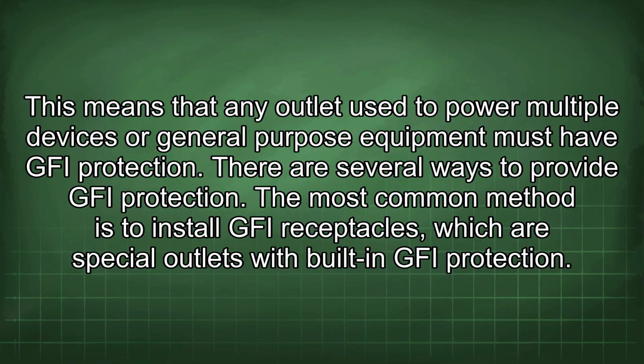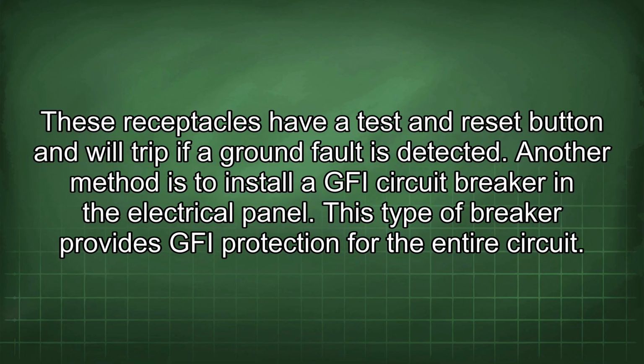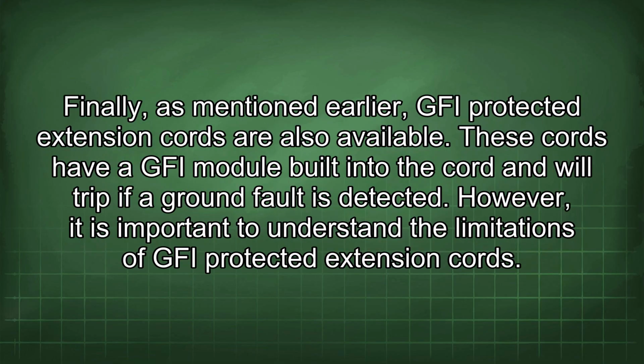There are several ways to provide GFI protection. The most common method is to install GFI receptacles, which are special outlets with built-in GFI protection. These receptacles have a test and reset button and will trip if a ground fault is detected. Another method is to install a GFI circuit breaker in the electrical panel. This type of breaker provides GFI protection for the entire circuit. Finally, as mentioned earlier, GFI protected extension cords are also available. These cords have a GFI module built into the cord and will trip if a ground fault is detected.